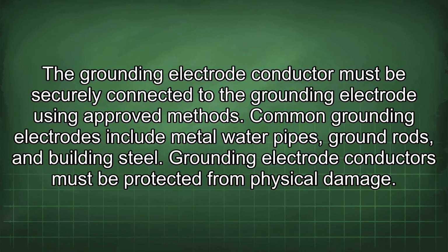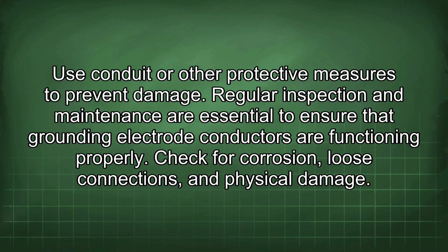The grounding electrode conductor must be securely connected to the grounding electrode using approved methods. Common grounding electrodes include metal water pipes, ground rods, and building steel. Grounding electrode conductors must be protected from physical damage. Use conduit or other protective measures to prevent damage. Regular inspection and maintenance are essential to ensure that grounding electrode conductors are functioning properly. Check for corrosion, loose connections, and physical damage.